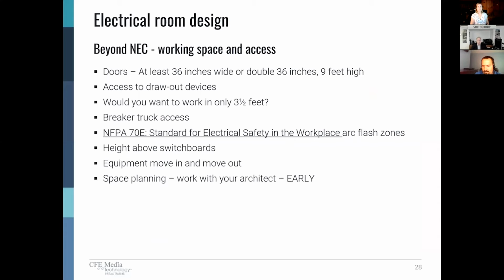Okay, so we mentioned all the code, and I touched briefly on the fact that the NEC is a minimum required established by the code bodies. It's not necessarily the best engineering practice. It's not always what you should just stick to. James mentioned the 24-inch doors. In my experience, going to larger doors is always the way to go. You've got to get that gear in and out. Move-in paths are something that we don't normally think about. We think about the room, right? How are we going to fit it?